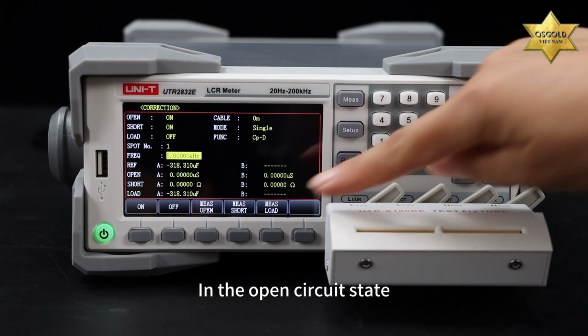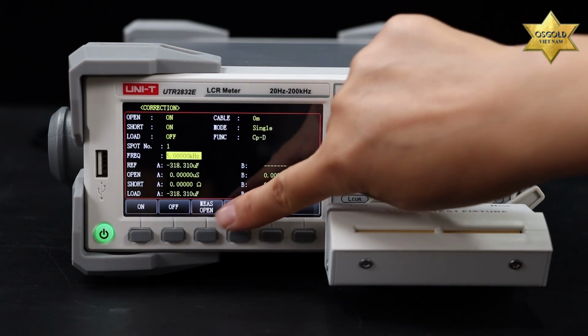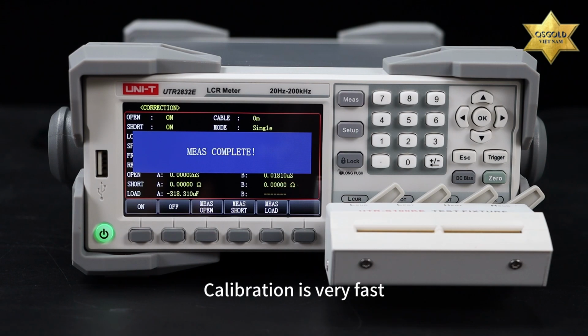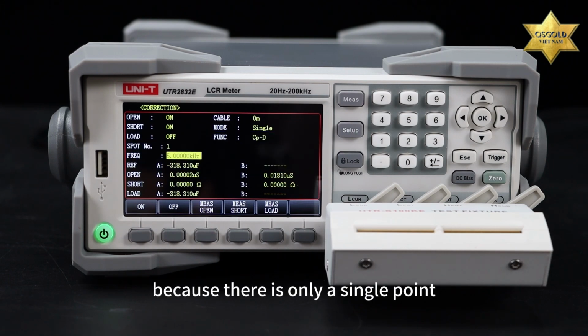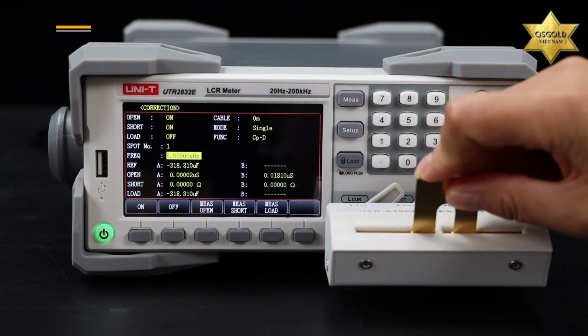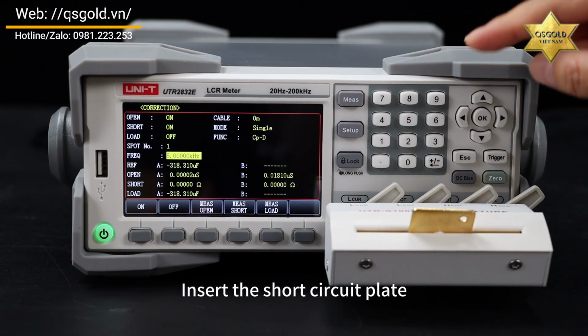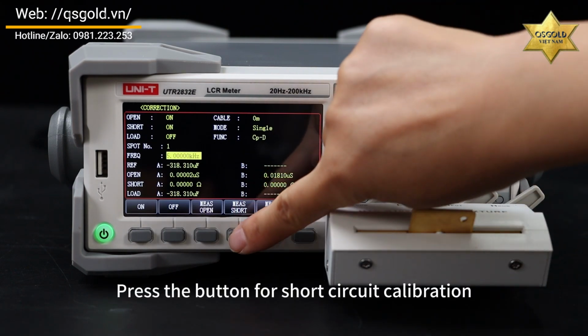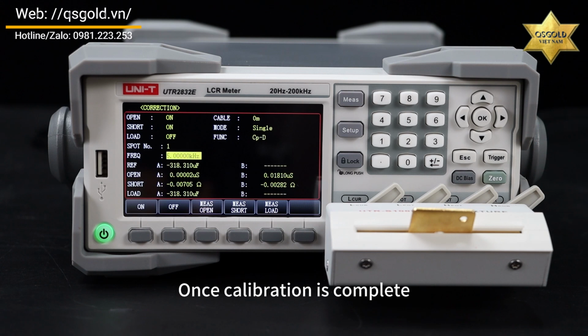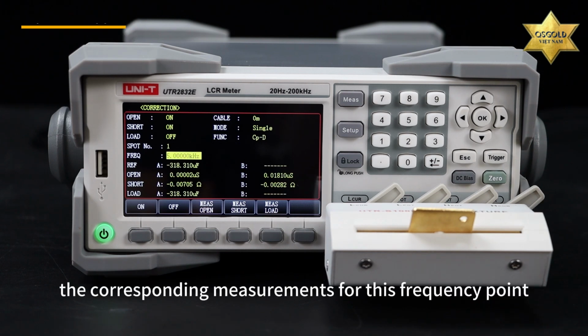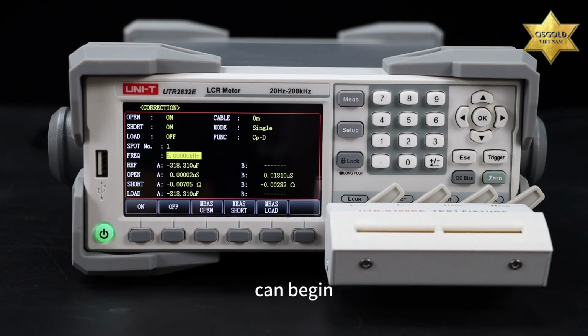In the Open Circuit state, click Open. Open Calibration. Calibration is very fast because there is only a single point. Insert the short circuit plate. Press the button for short circuit calibration. Once calibration is complete, the corresponding measurements for this frequency point can begin.